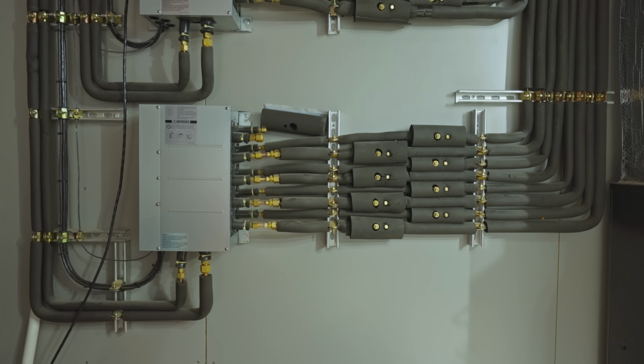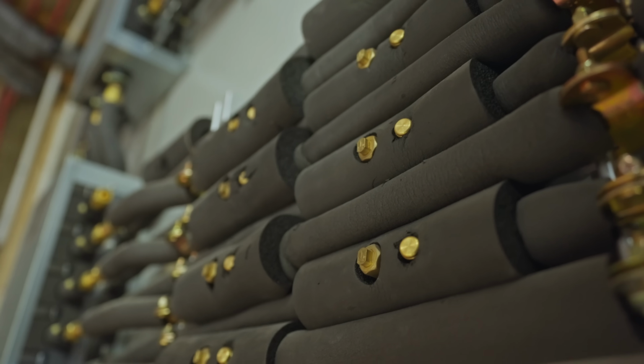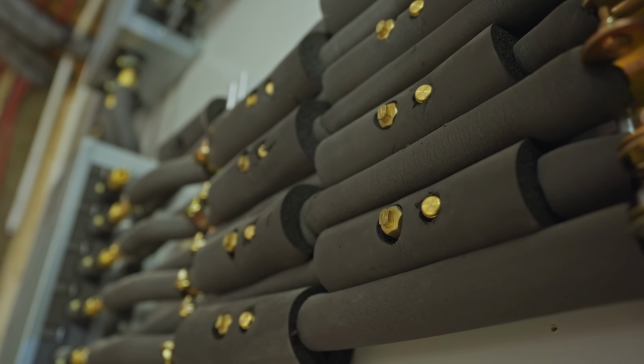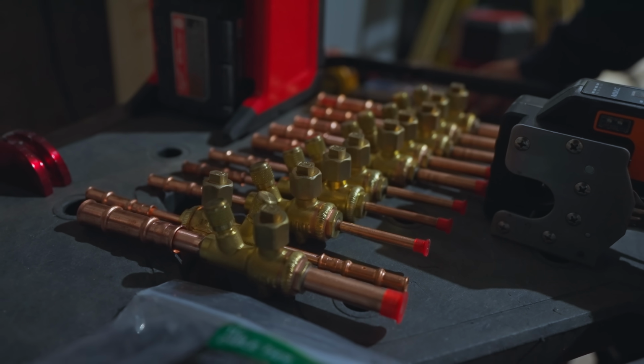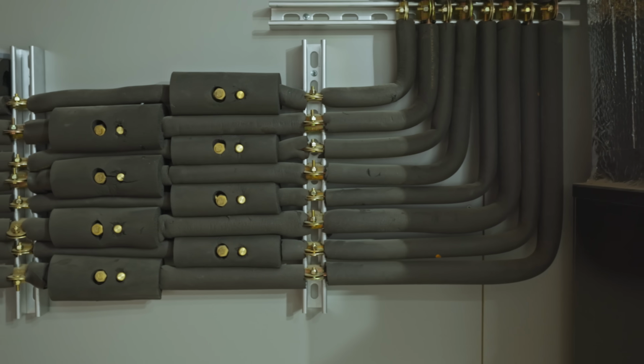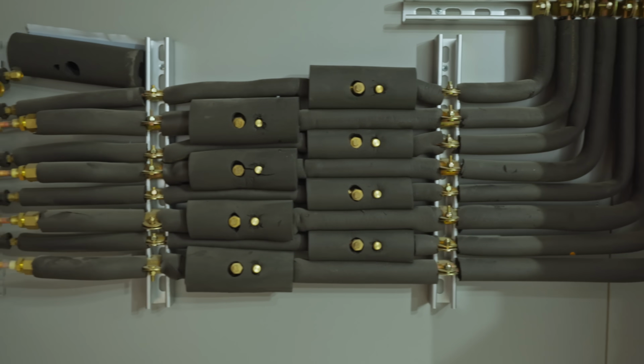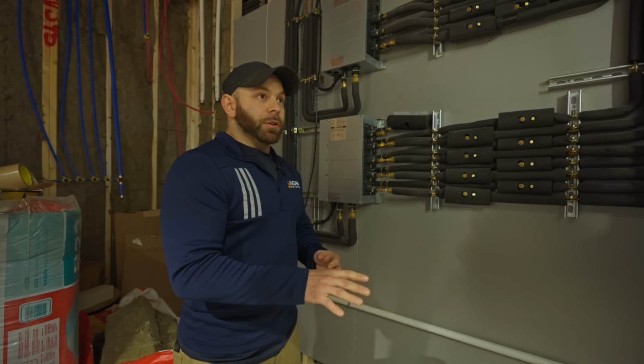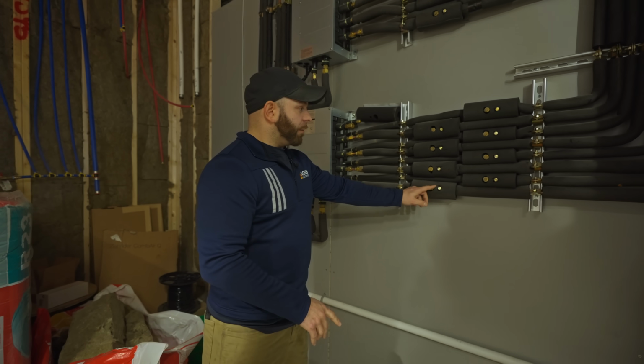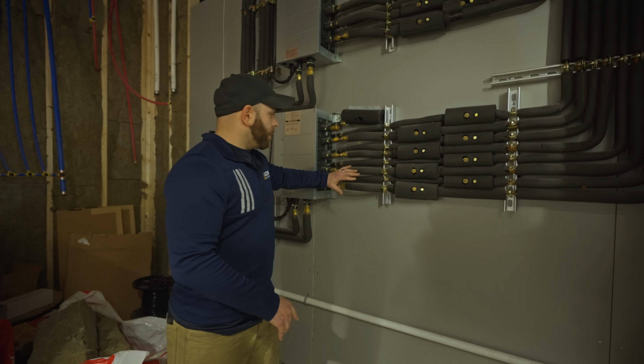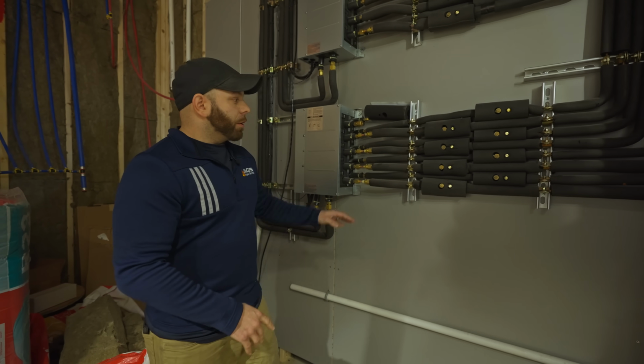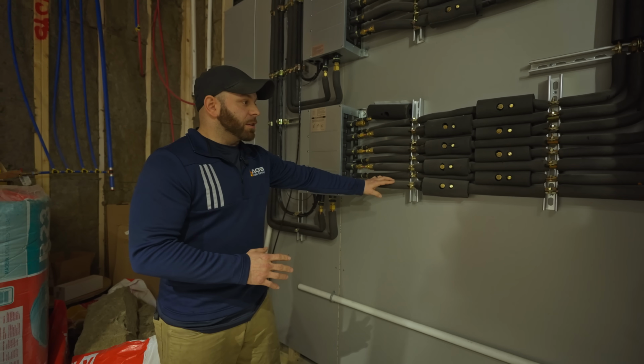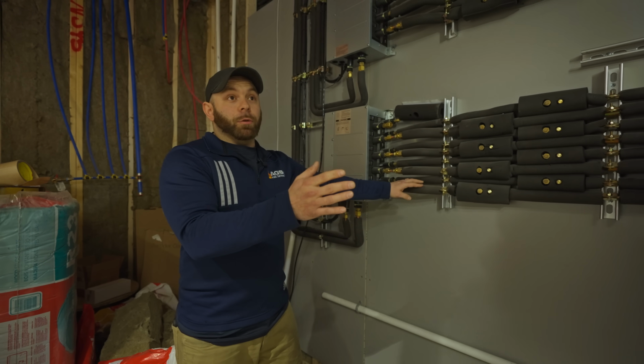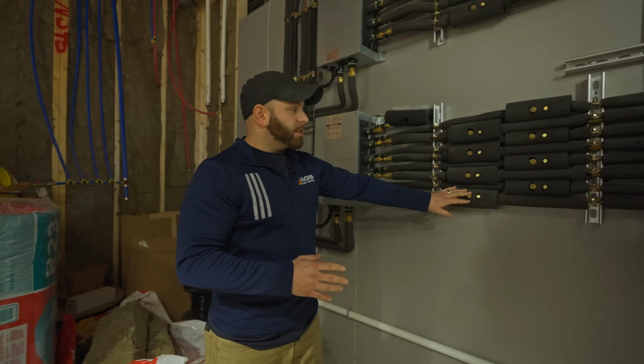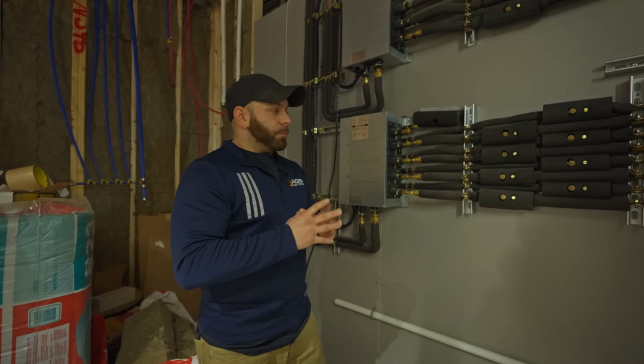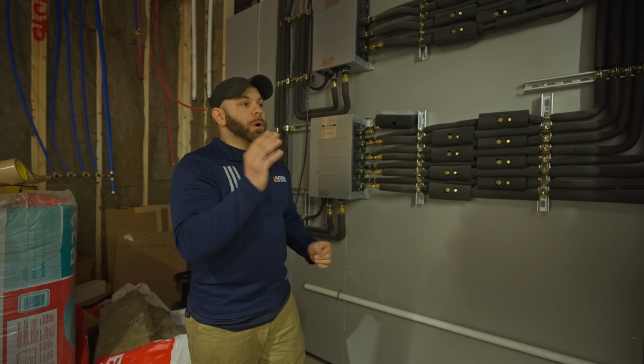What is all this? This isn't something you typically see in residential construction—what is it and why is it important to you guys? We decided to do this because if we need to work on a unit in the future, from here we can isolate the system and still have it running while working on that one unit. We can just shut off each one depending on which is connected. Let's say this one is connected to the downstairs unit—if there was something wrong with the coil, we'd isolate this unit and keep the whole system running while working on it.